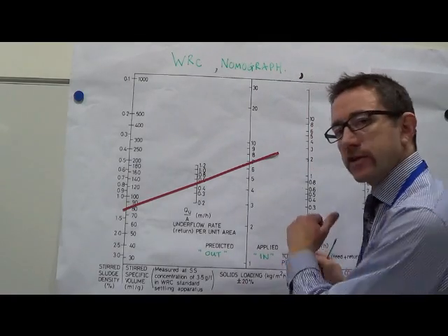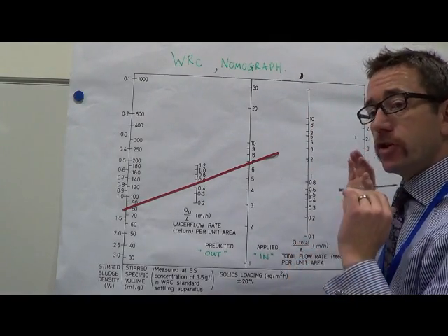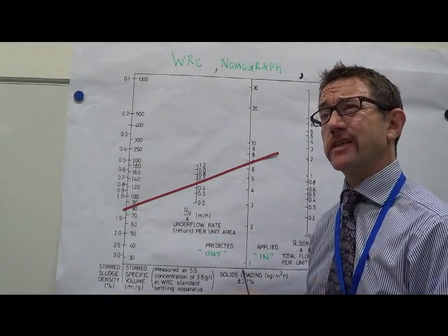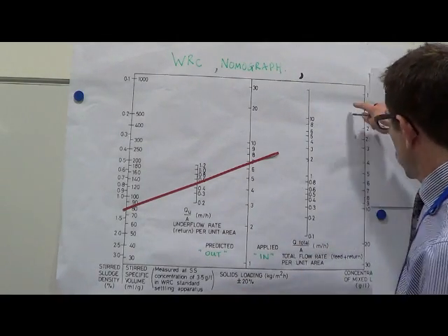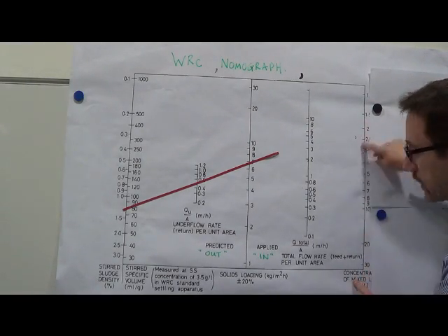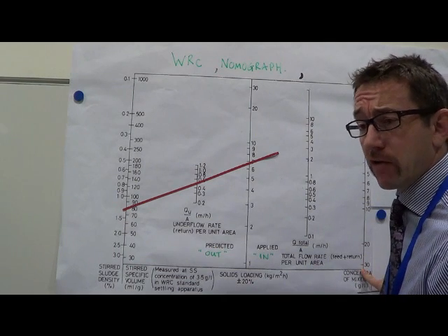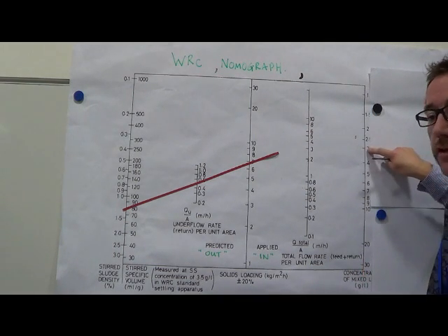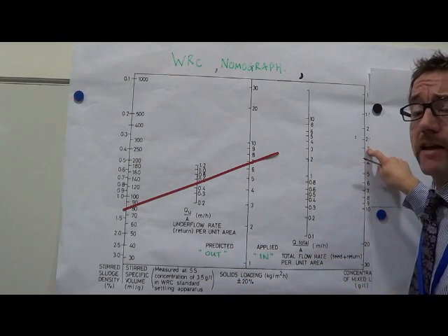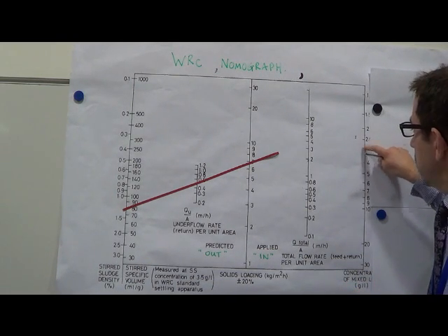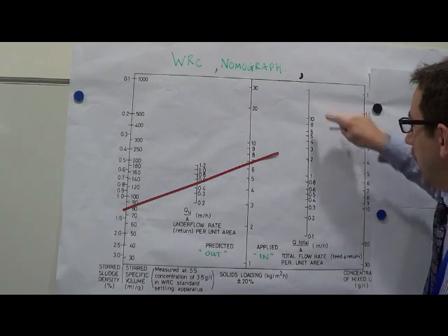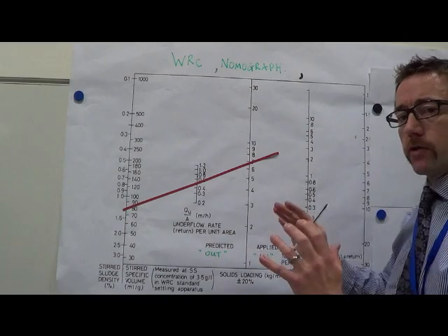Easy. Right, the other side of the equation is how much you are trying to put onto that final tank. And again, you shouldn't be surprised at the sorts of things that crop up there. So, what's the mixed liquor suspended solids? That's measured here in grams per litre, as we talked about earlier on. So, for example, 3 is 3 grams per litre of mixed liquor suspended solids, which means 3,000 milligrams per litre in our old money. So the more solids you have, the more you're going to ask of your tank. And then this is how much flow you've got going on to your final tank.